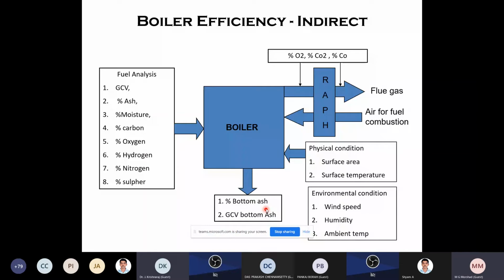Then you have to take the bottom ash sample, the percentage of ash and GCV of the bottom ash. Then you have to get the flue gas analysis, percentage of oxygen and carbon dioxide, before and after the air preheater. Then the surface area and surface temperature of the boiler, then environmental conditions: wind speed, humidity, ambient temperature. So you have to collect all the data first, and only then can you go for the indirect efficiency of the boiler. It's a very typical and complicated method. So during an energy audit, we should insist they carry out this indirect report.